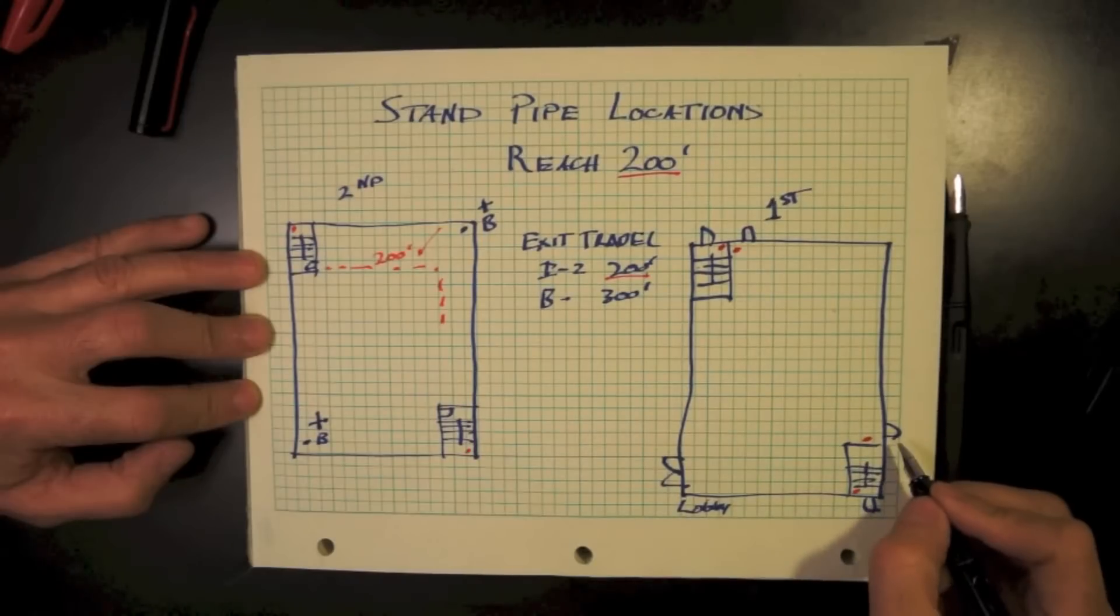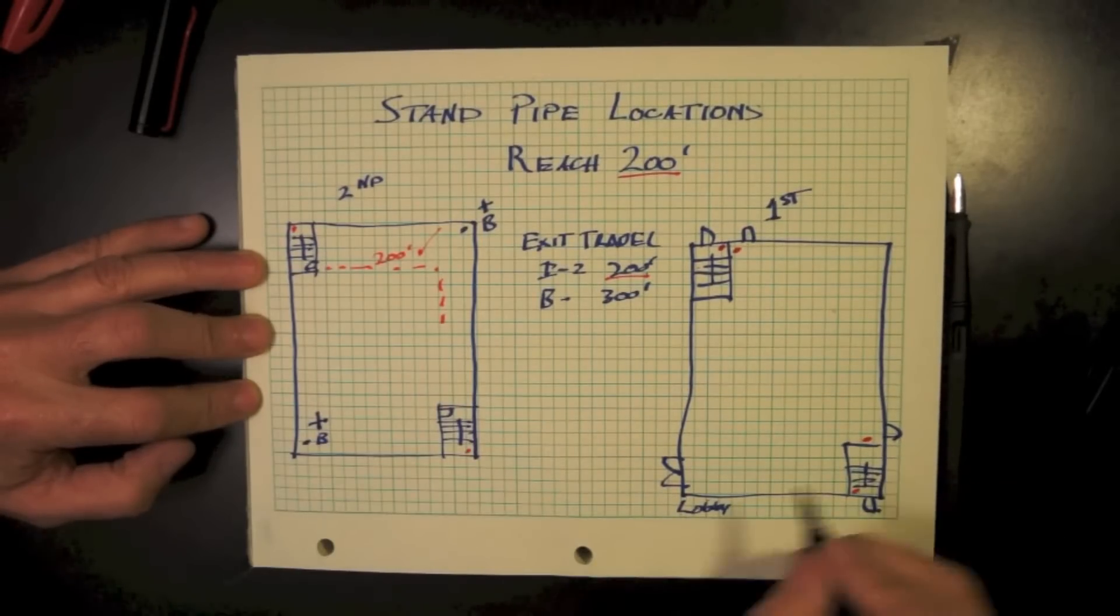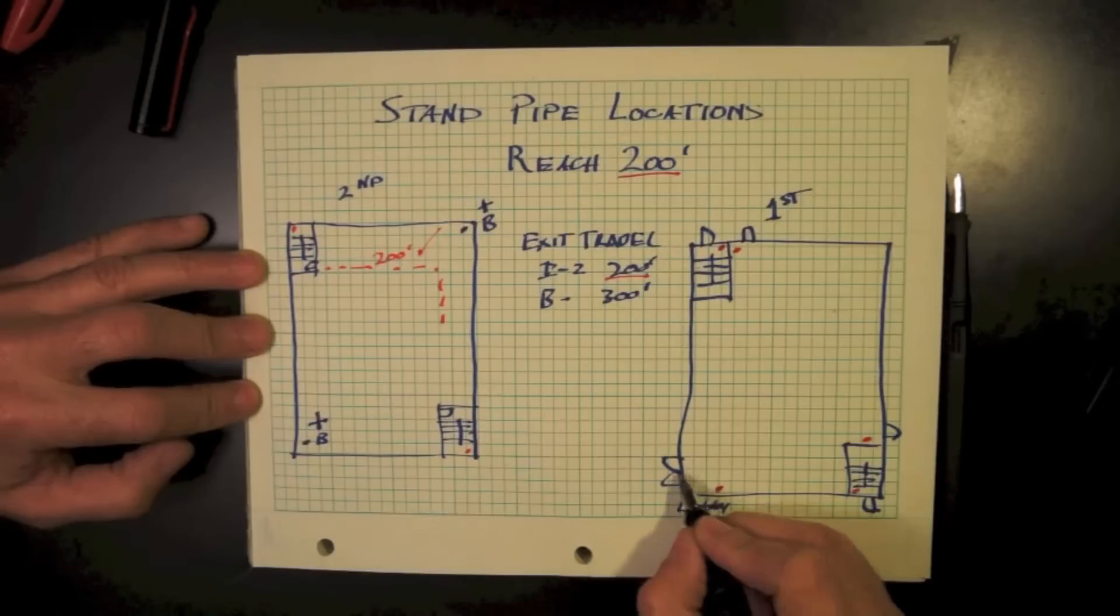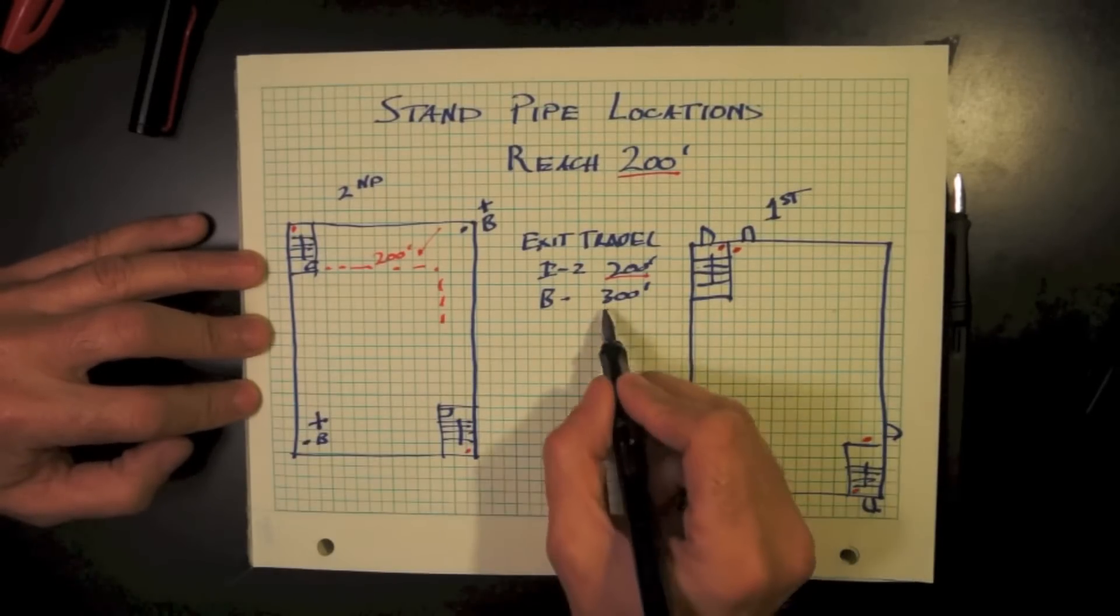More particularly, what I've seen in various buildings is the lobby is forgotten about, and a standpipe really should be located fairly close to the entrance. Additional standpipe topics are coming in forthcoming videos, including horizontal exits.